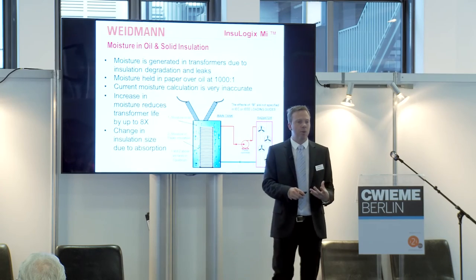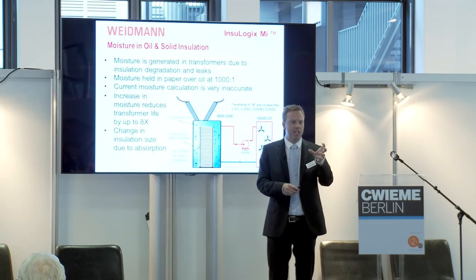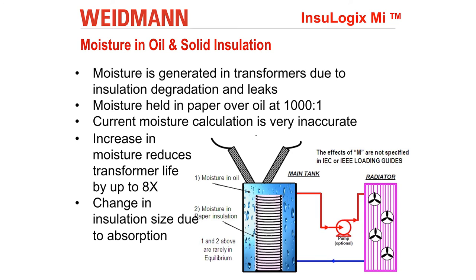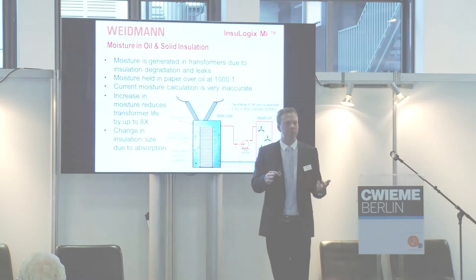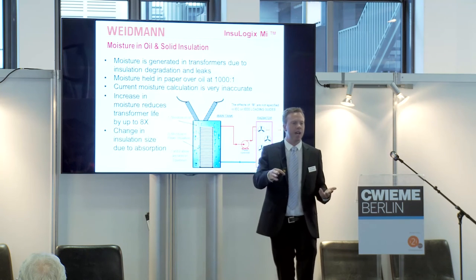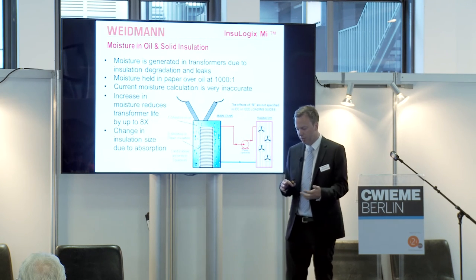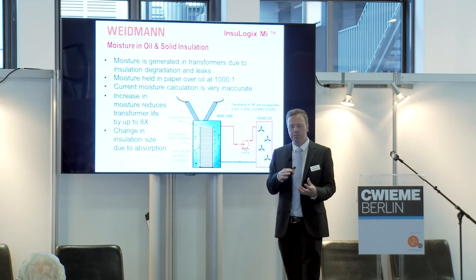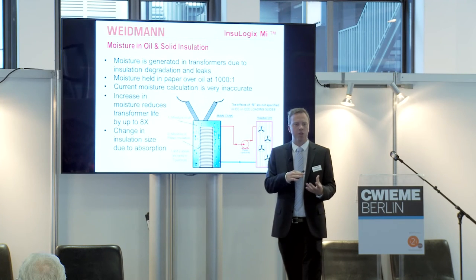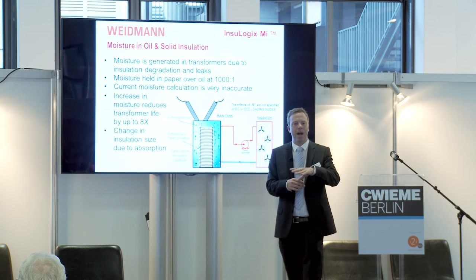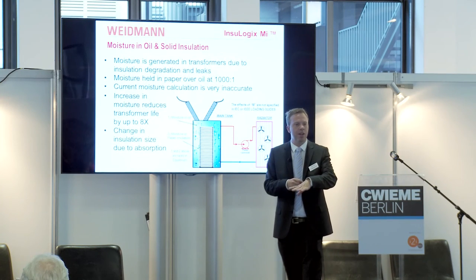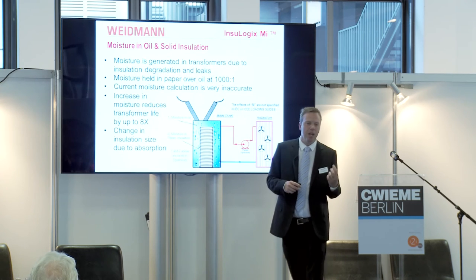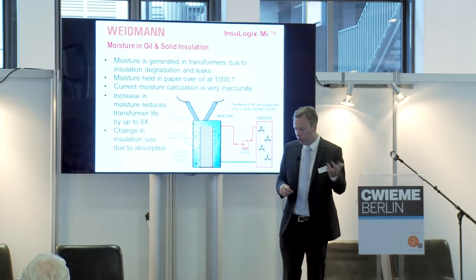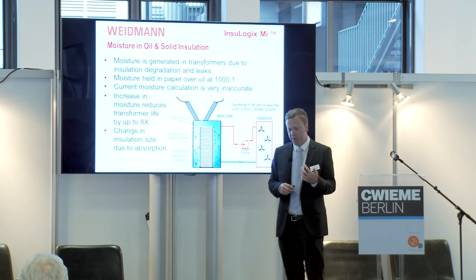So as a transformer ages and the gaskets start to corrode somewhat, you may have moisture ingress through these areas. Thirdly is the cooling system. Again, as the transformer ages, you may have some water ingress through the cooling system. So the content of moisture in the transformer will change throughout its life. And as we talked about, that content of moisture directly impacts the breakdown of the insulation and can cause the transformer to fail.